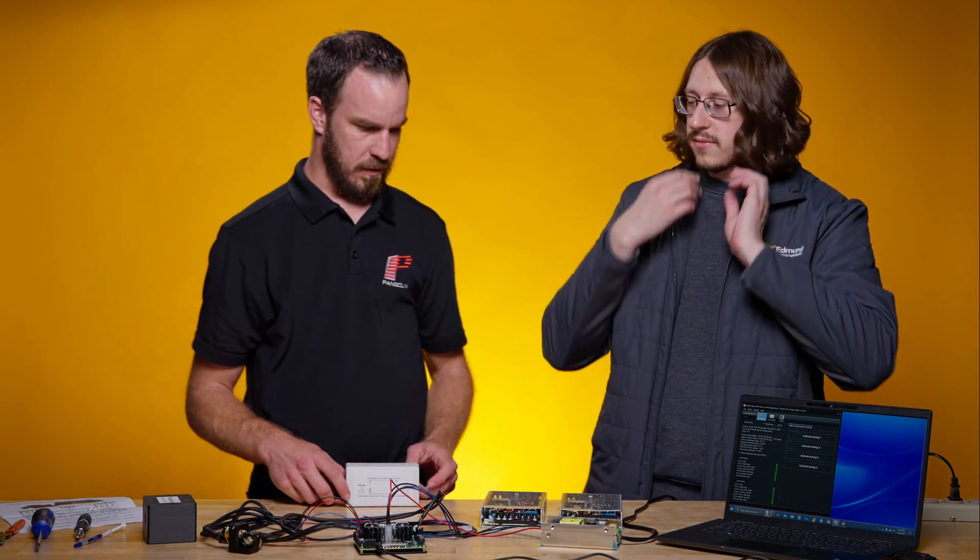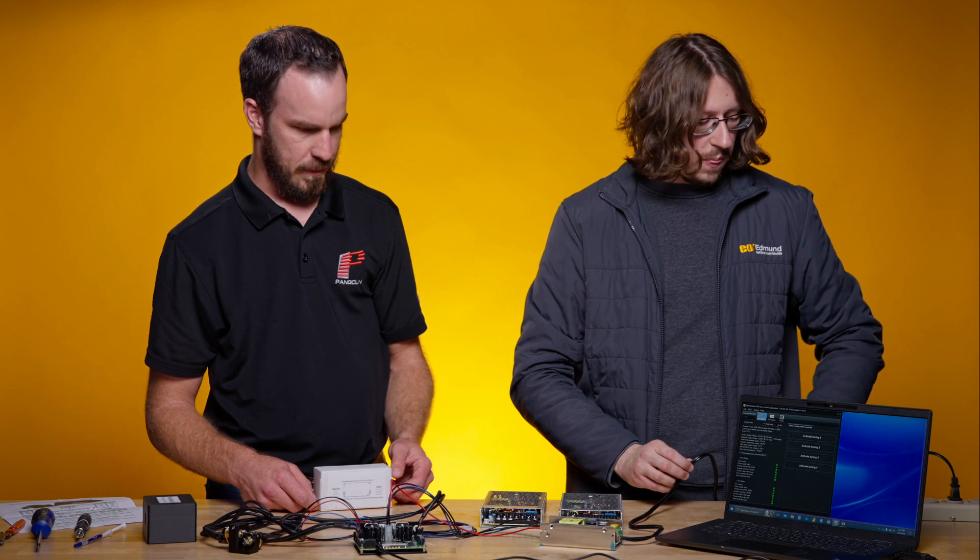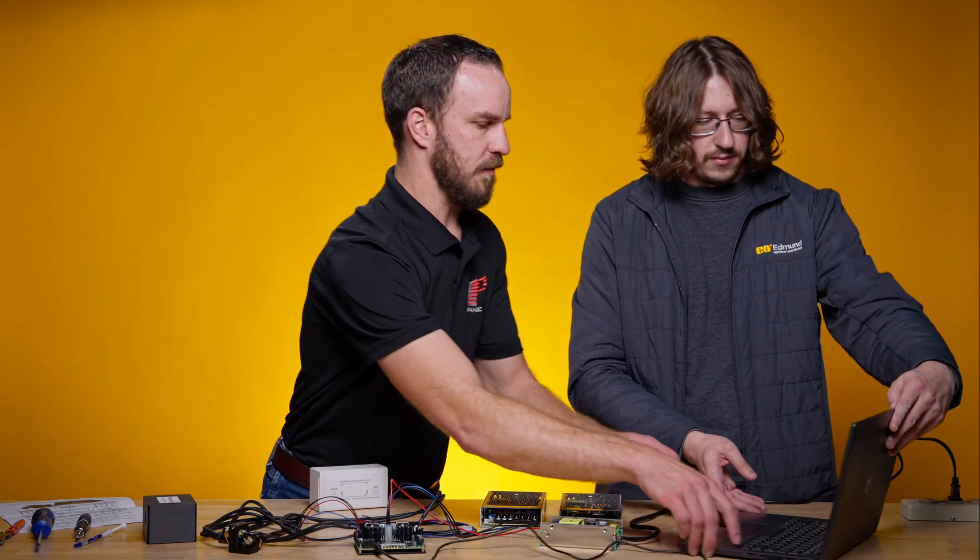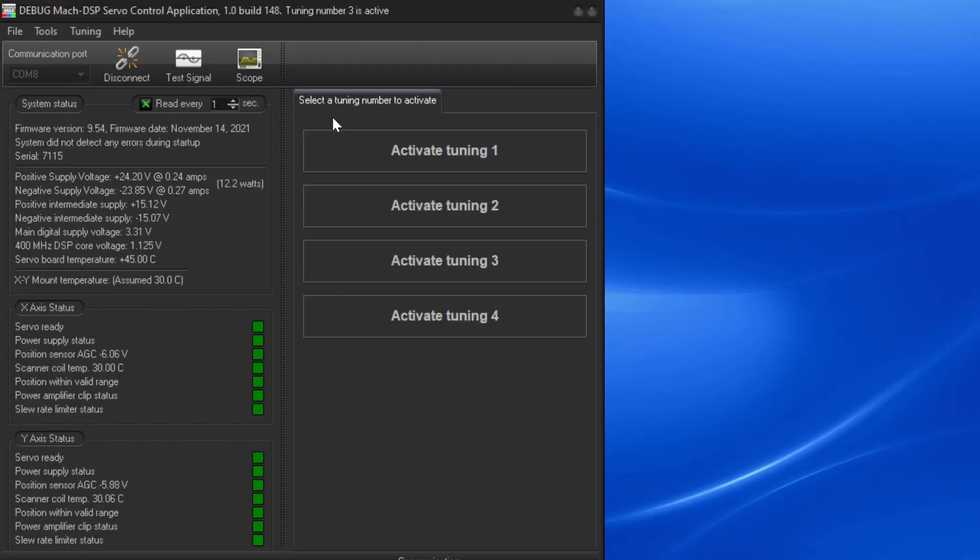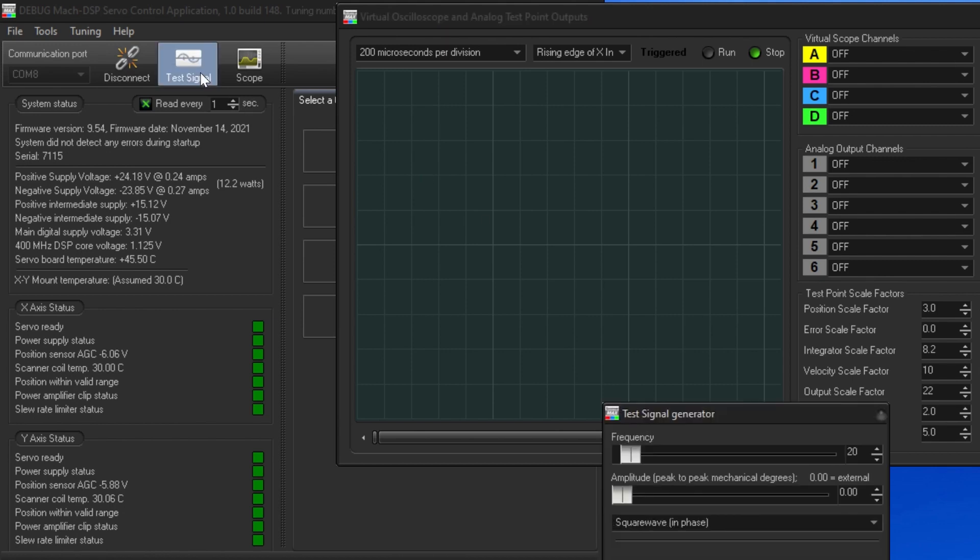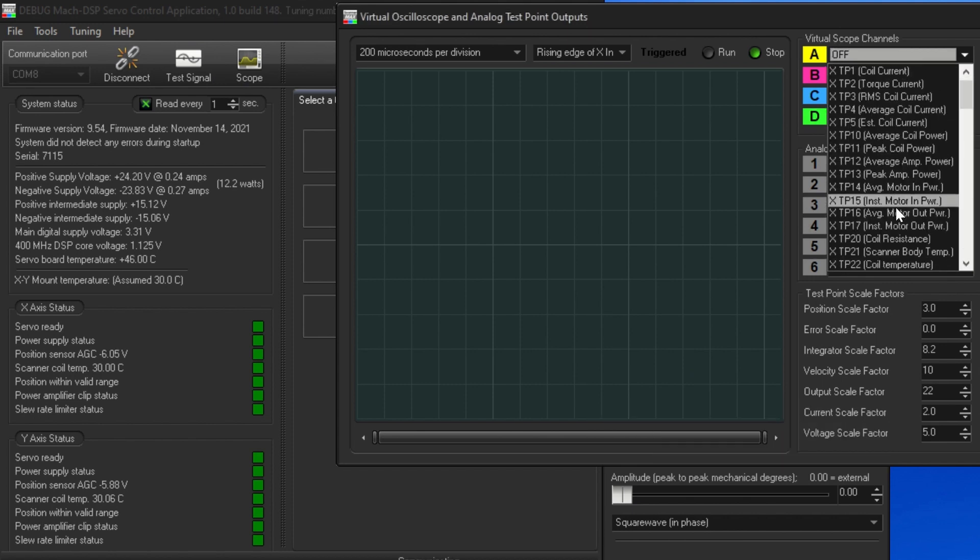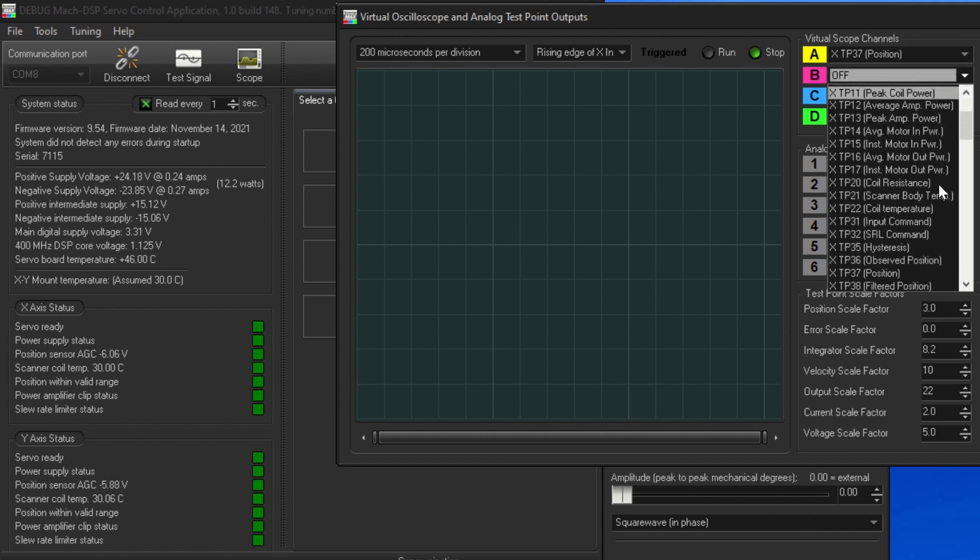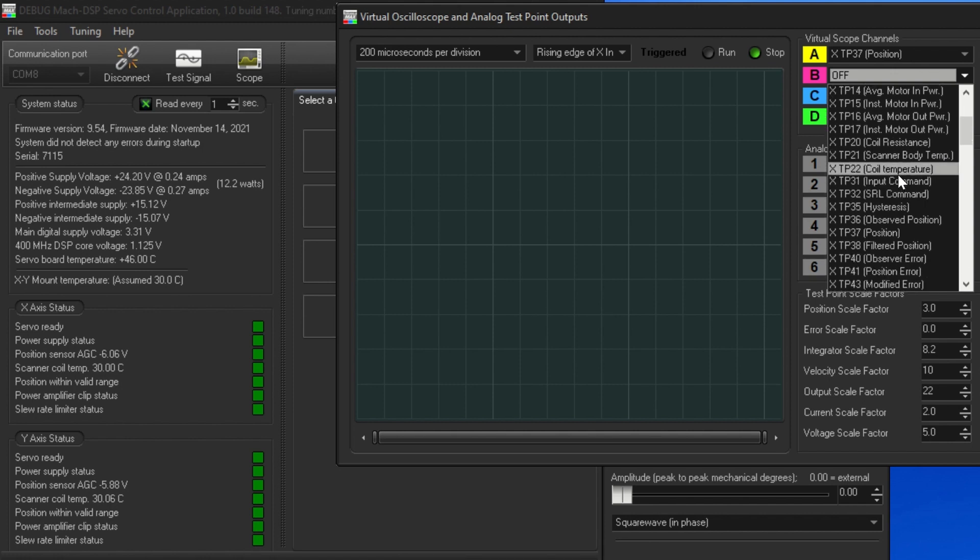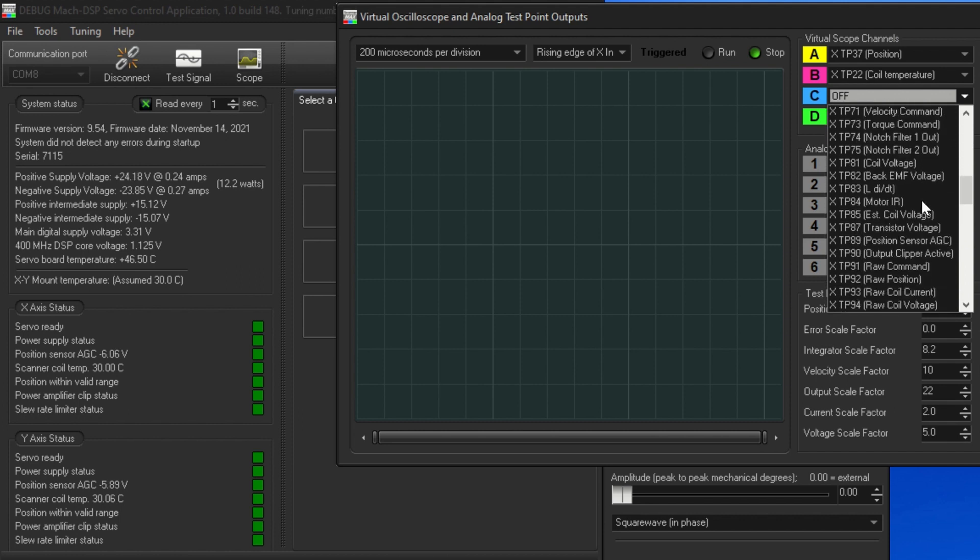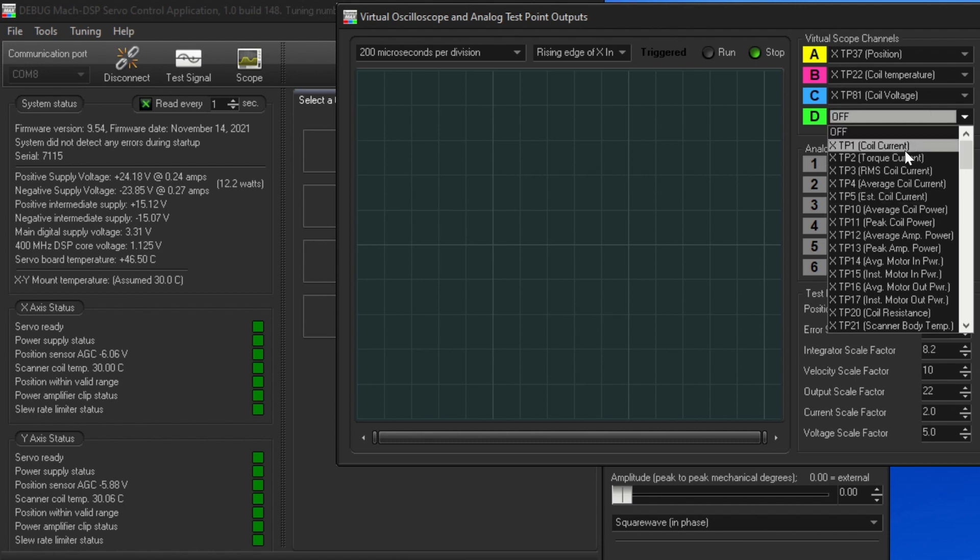And once it opens up, it opens up right to the four tunings that come standard with every EO system. So Ryan, why don't you walk us through what the tunings are? Okay. Thanks Jacob. Yeah. We'll do a quick run through of the software on the tunings. Again, the Mach DSP software downloaded from Edmund website. When you fire it up, this is what you're going to be seeing as the user interface. It's pretty powerful software for what it is. You get a built in oscilloscope. I think you can sample a hundred test points per axis, something like that. You also get a built in test signal generator. So for the purpose of this demonstration, we're going to check out the X Galvo. Maybe we'll want to see the X Galvo, we'll want to see the Galvo position. Maybe we'll take a look at what the actual commanded position is. Input command. Maybe we'll keep an eye on coil voltage as well. And maybe we'll keep an eye on coil current as well. Go ahead and hit run.